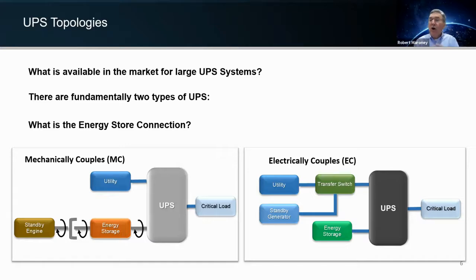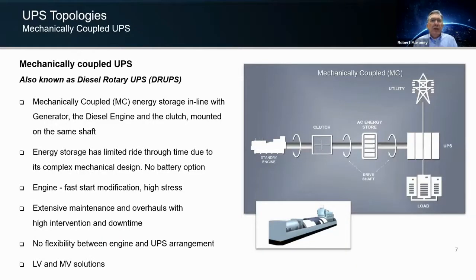So you have a utility with an automatic transfer switch, okay, that's connected to a genset for your long-term or alternate power. And then you have that connected to the UPS. And then the UPS has got a DC bus, which connects to an energy storage device, thus protecting your critical loads. So we're going to talk about them in mechanically coupled versus electrically coupled format today for the most part. So here's a little more detail on the mechanically coupled, okay?